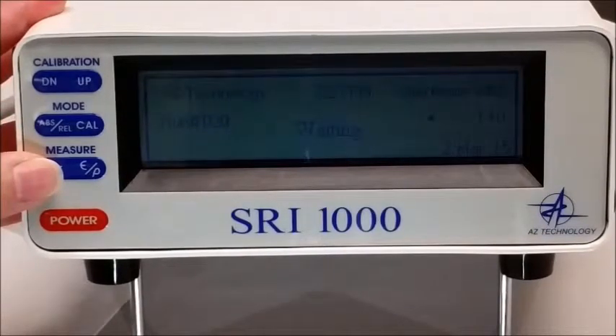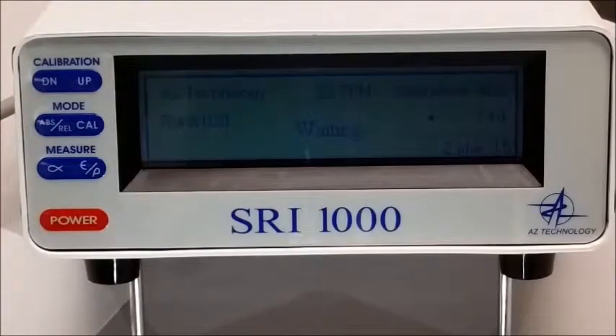After pressing the alpha button, both displays on the control display unit and the head unit will display waiting. The upper right-hand corner of the control display unit will display solar mode absolute. To initiate taking measurements, press the trigger located on the handle once again. The trigger has two functions. When the trigger is pressed in the wait state, indicated by the display of waiting, the instrument will switch to the measurement state and begin making solar absorptance measurements. The instrument then displays the alpha value.